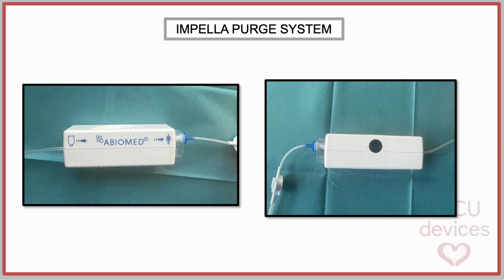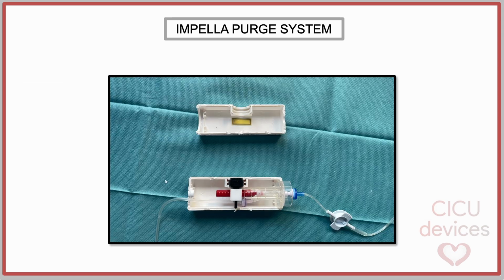Externally, the Purge Cassette has the shape of a quadrangular-based prism. On its posterior surface, it features an opening designed to engage with the console rotor, allowing correct mechanical coupling and fluidic actuation. Internally, the cassette features an internal channel architecture that guides purge fluid flow through the cassette, along with a syringe-like embolus mechanism.